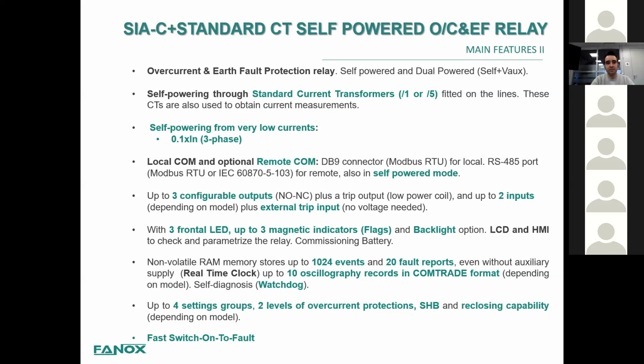It's very important to have different setting groups, because depending on how you energize or first commission the devices, you may have separate setting groups: one for normal behavior of the installation, a second one for maintenance purposes, and maybe a third one to allow some overcurrents during the first energization. And you can change easily between these three setting groups by means of inputs with a selector. It gives more flexibility to our relay to cover all of these situations.